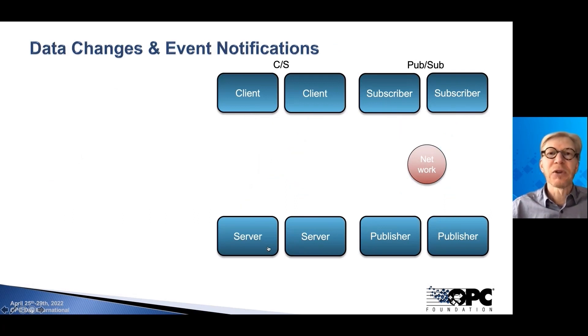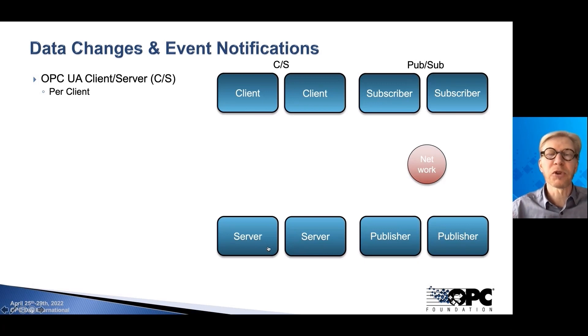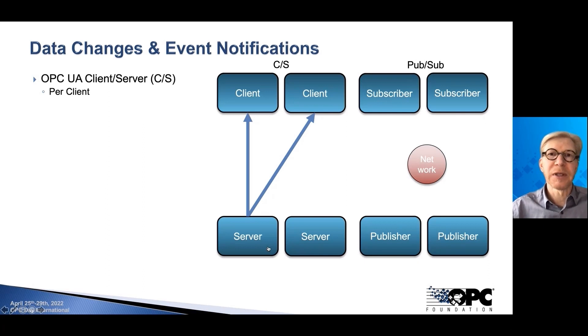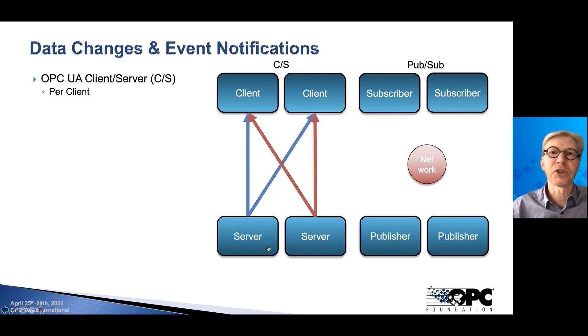Looking at data changes and event notifications — the basic data monitoring applications do with each other — we already have this established in client-server communication through subscriptions. The issue there is that these subscriptions are defined separately for each client. It's good that every client can define what they want from the server, but servers need to take care of all clients separately. When we add another server we get another set of subscriptions, and if we get more clients, the servers get more loaded handling all the connections.